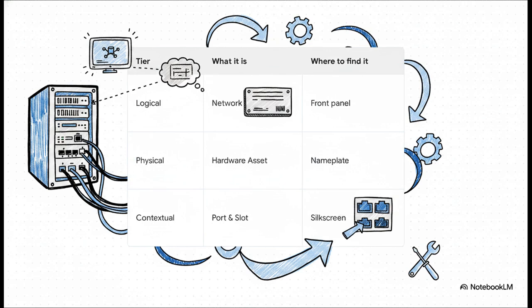Tier 3 is contextual: where's the specific port or slot located on the chassis? For this, you have to verify the silkscreen printing directly on the faceplate. Because if you report a fault on port 3, but you're actually plugged into port 4, you're going to waste hours troubleshooting a perfectly working port. You absolutely must verify all 3 tiers.